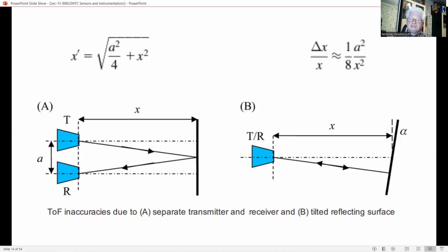A transmitter emits a short pulse, a few up to about 10 periods of a sine wave, in the direction of an object. The sound reflects in accordance with the reflection properties of the object surface and its orientation. As discussed earlier, it travels back and is received by the same or a second transducer, which detects the moment of arrival. Due to various causes, the accuracy of the TOF measurement, and so the distance measurement, is limited. First, there is noise of electrical and acoustical origin, which becomes important at larger distance, when the echo signal is low due to the divergence of the sound waves.